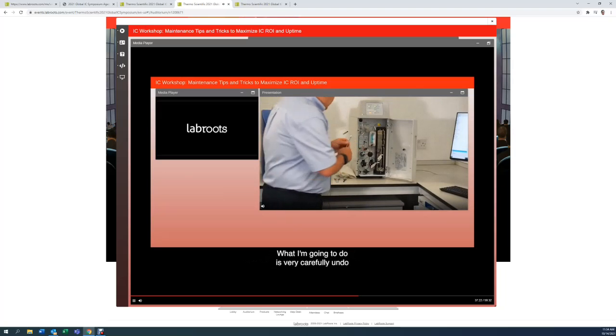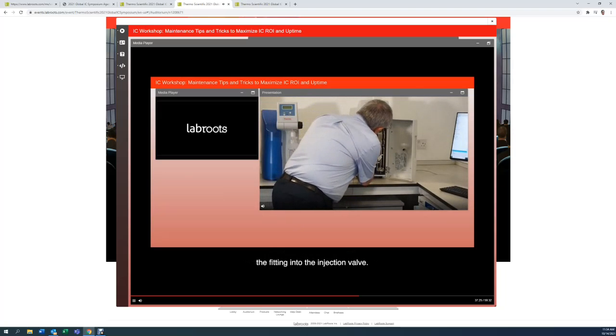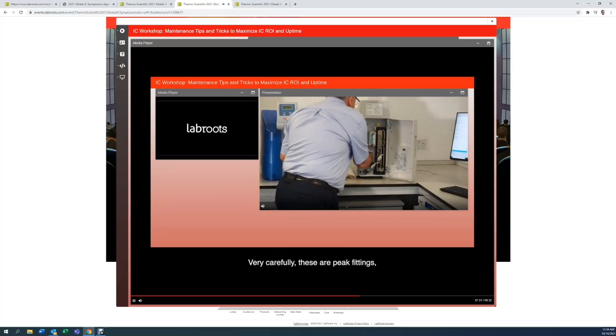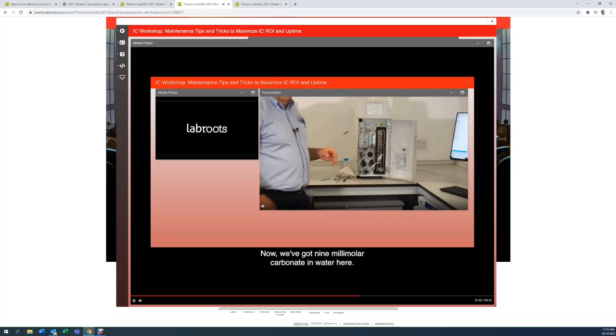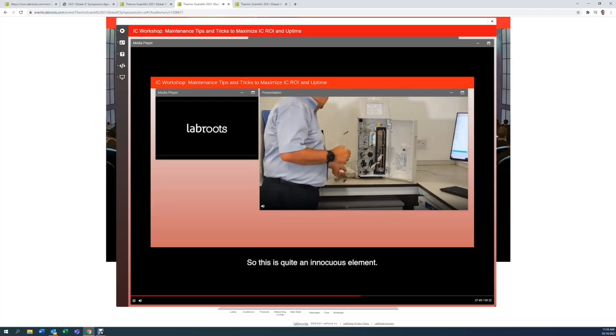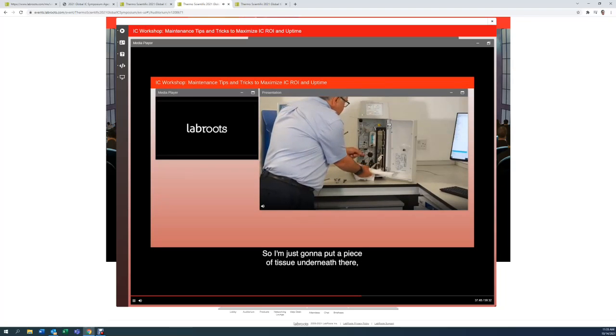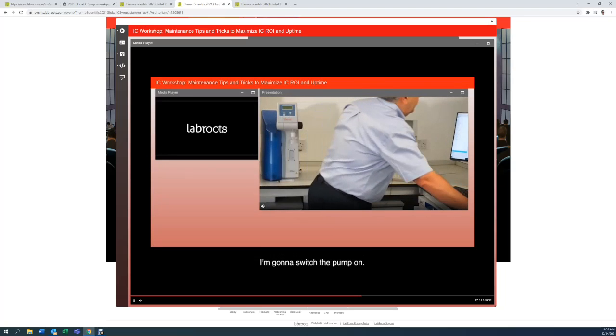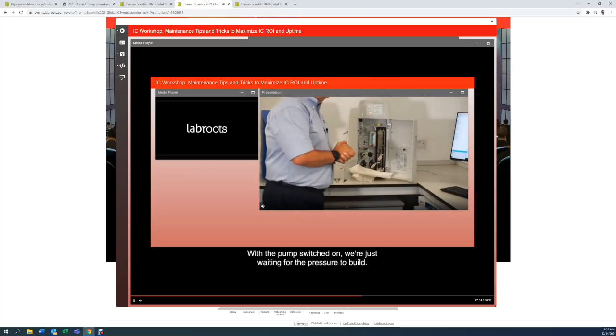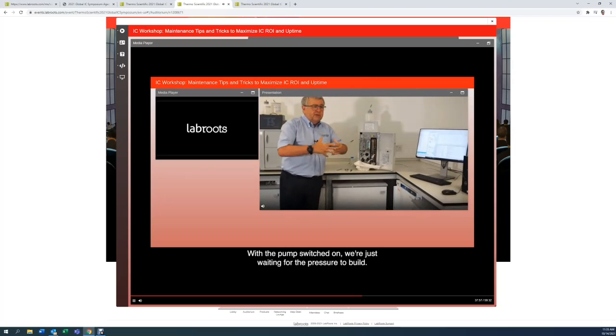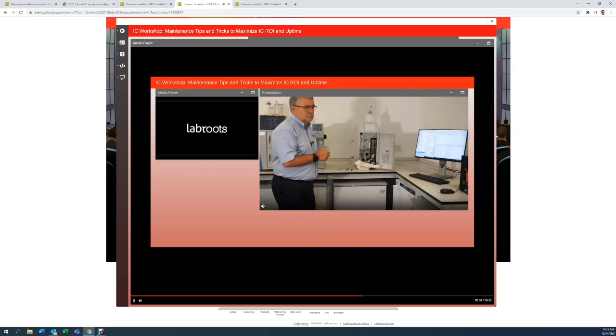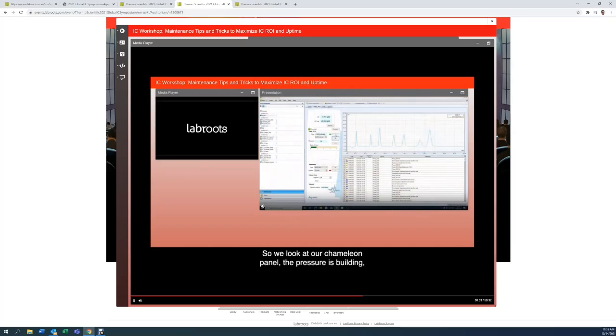So what I'm going to do is very carefully undo the fitting into the injection valve. These are PEEK fittings, so a bit of care is needed to make sure we don't damage them. Out it comes, and there it is. Now, we've got 9 millimolar of carbonate in water here, so it is quite an innocuous eluent. So I'm just going to put a piece of tissue underneath there. I'm going to switch the pump on. And with the pump switched on, we'll just wait for the pressure to build, and let's see what it gives us. So we look at our Chromeleon panel.